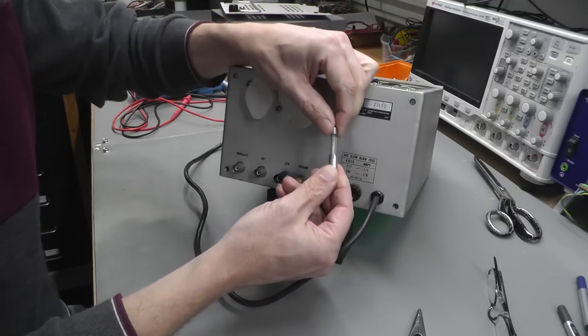Now the next thing I'm going to do before we actually power up—I need to look at the back of the unit here. We've got this fuse holder here. No, it doesn't look like a fuse holder, but it is. The black cap is actually missing from the fuse holder, and actually this is live. If I just remove that, there's the fuse there. It's just the metalized cap that goes inside the plastic cap. So that's a little bit dangerous. So I'm going to have to change out the whole fuse holder. And we've got a couple of banana plugs next to it. This one here is missing the green shroud for the four millimeter banana, so I'm just going to change out the whole thing. Because I'm changing out that one and it's got to be nice and level with the black one, I'm just going to replace them both.